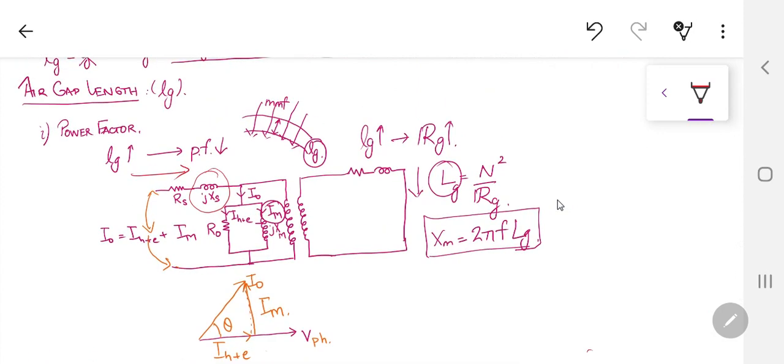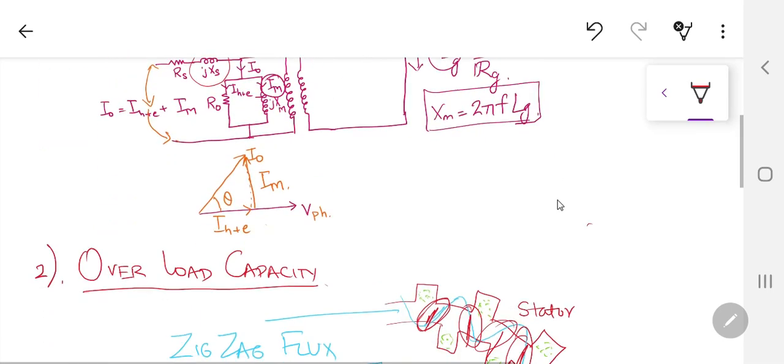But of all four factors we have just discussed, the most important one is the power factor, because power factor is the more electrically dominant factor. Certainly, if your power factor is on the lower side, your efficiency is also going to be lower, because a lot of reactive power is going to be consumed. So you are going to have the expense of a penalty, or the expense of power factor equipment, if capacitors or something like that have to be added.